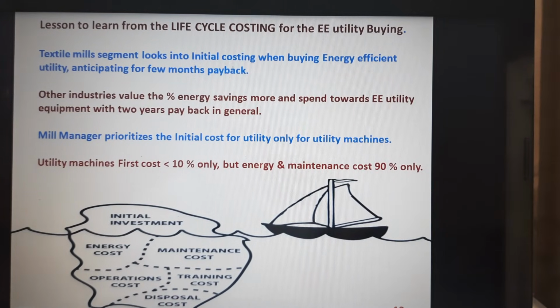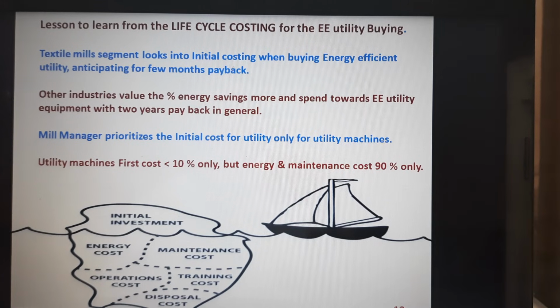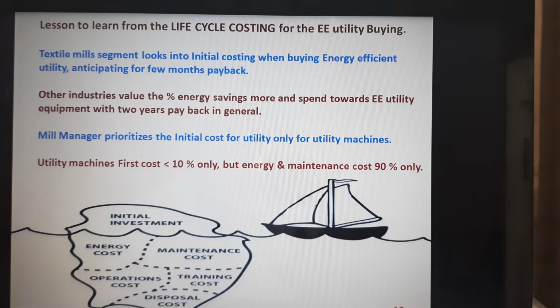Let us learn from life cycle costing, especially when we are buying energy efficient utilities. The textile mills always look into the initial cost when you buy a utility machine. But when you buy a production machine, you go for a higher price, you go for a higher productive machine. When you go for a utility machine, you always look for an excellent efficient machine, where the first cost is only less than 10%, but the energy and maintenance cost is more than 90%. So the mill manager needs to give priority to the total life cycle cost of the utility machine, which is to be matched to the production schedules as such.